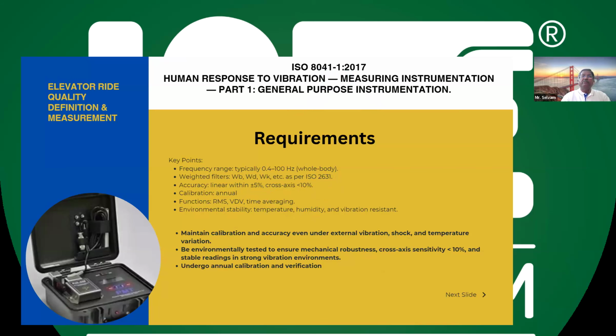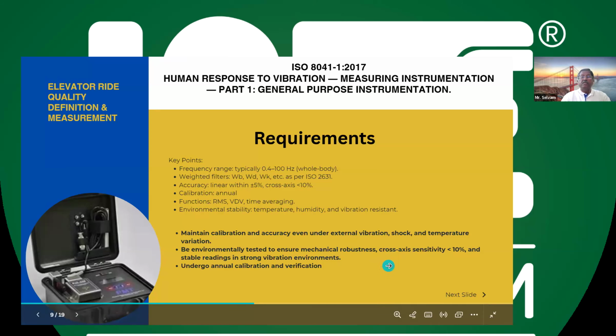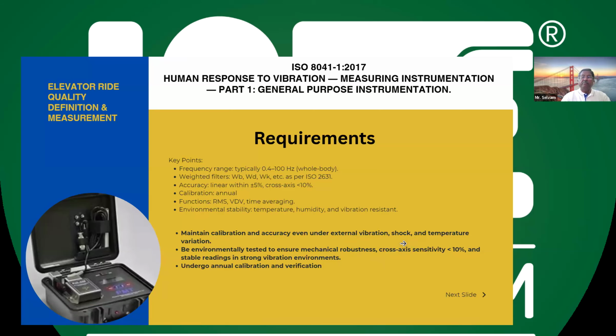For example, when you want to measure the vibration under normal condition, and also sometimes during a safety gear test or emergency, whenever, in our India, power supply can fail at any time. When it's going at very high speed, suddenly power supply can fail. So the lift will be stopping at very high speed. So there will be very high shock, and temperature can vary, like in Nagpur and all. In summer it can go to 50 degrees, and in Delhi and all, in winter it can go to maybe 4 degrees, 3 degrees. So it has to work under different temperature conditions. Now that is in our country, but in other areas it may be a wider range.